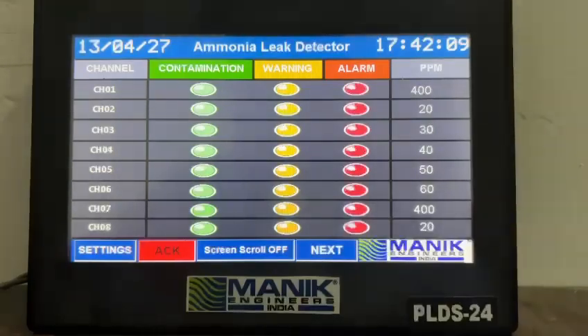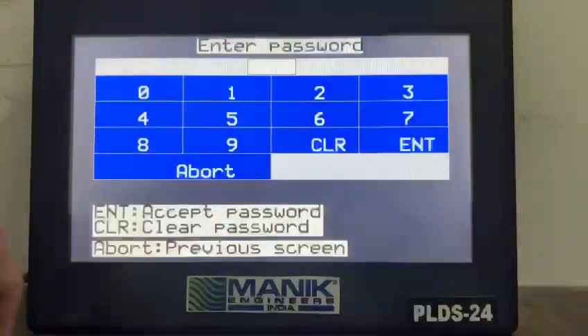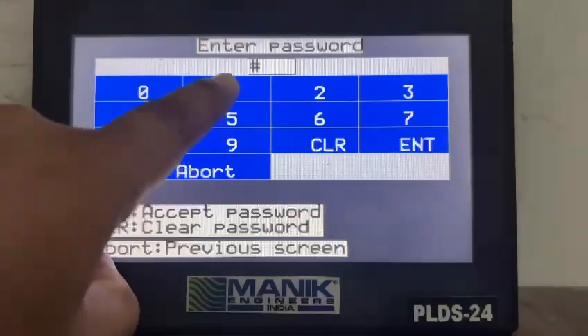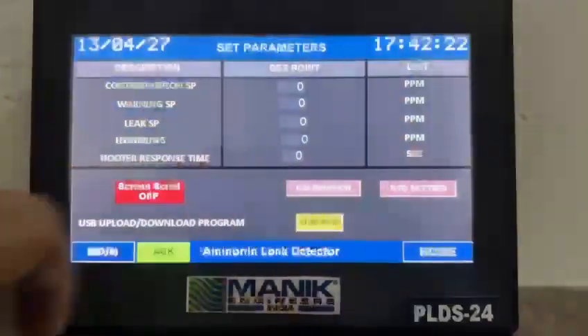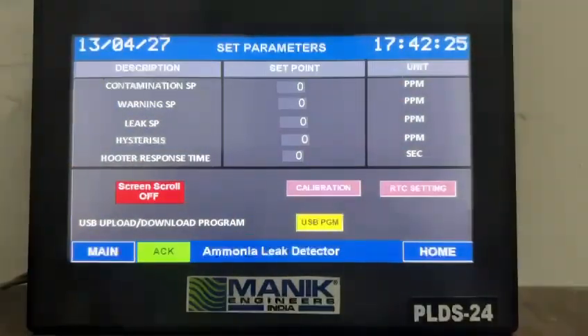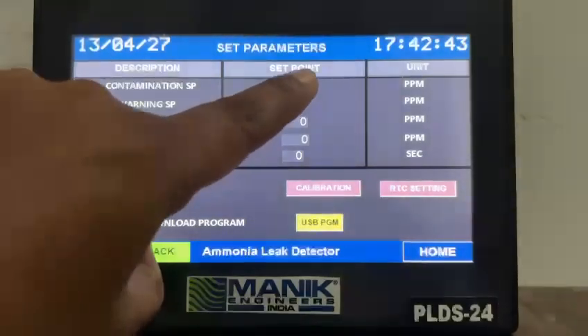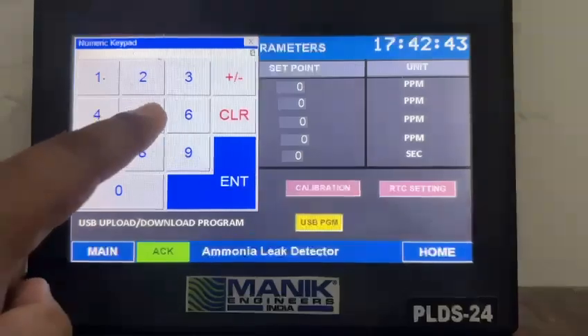Touch the setting button to access the setting menu. Once you touch the setting button, we have a pop-up screen here for entering the password. Once the setting screen is visible, we have the following options available: contamination set point, warning set point, leak set point, hysteresis set point, and hooter response time set point. Just touch on the contamination set point to set the contamination threshold value.